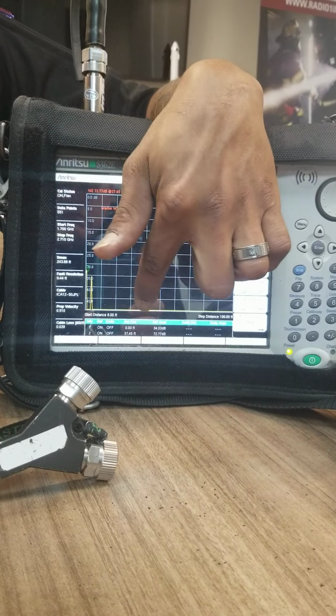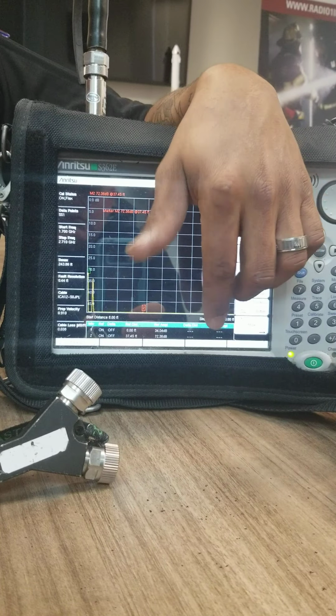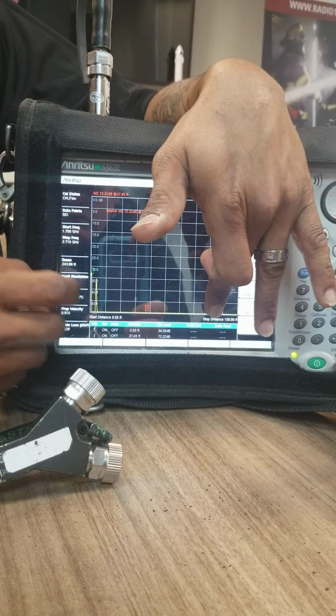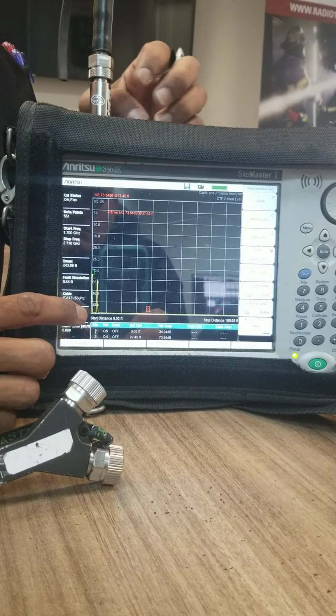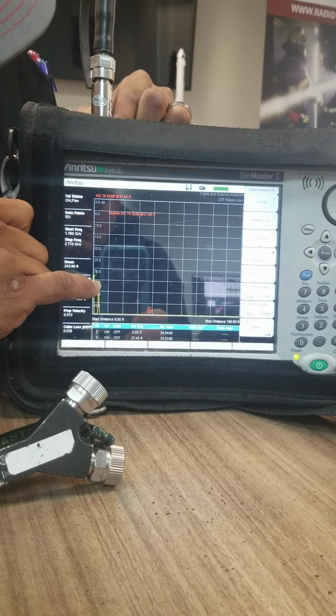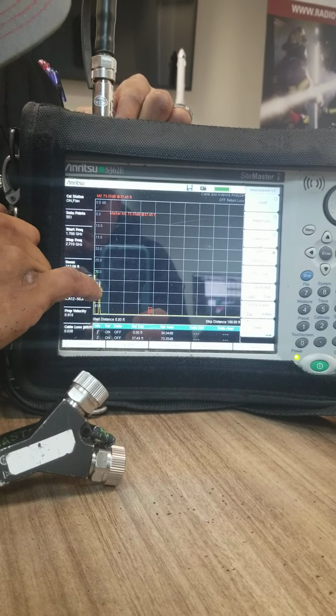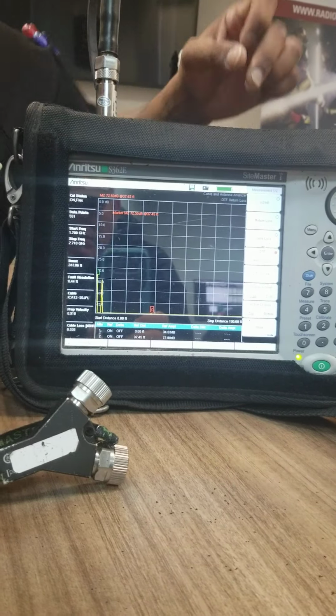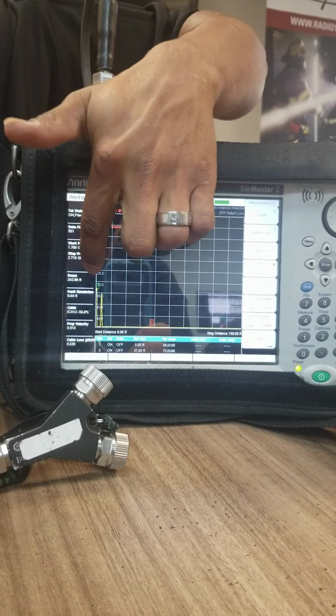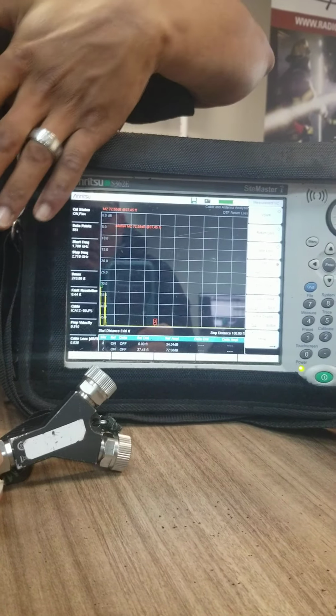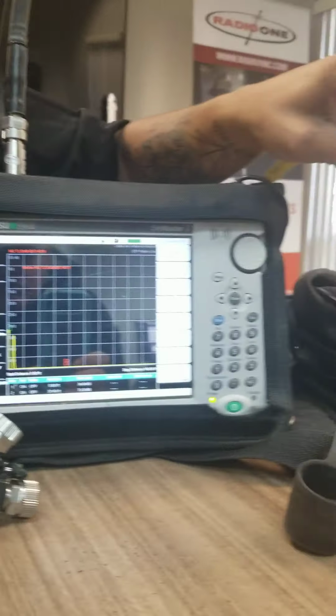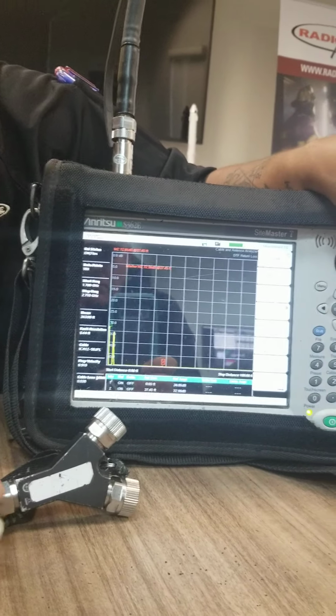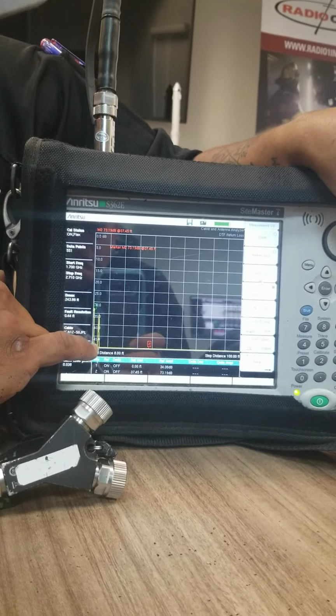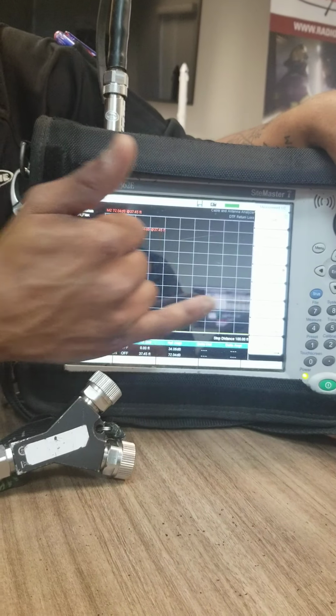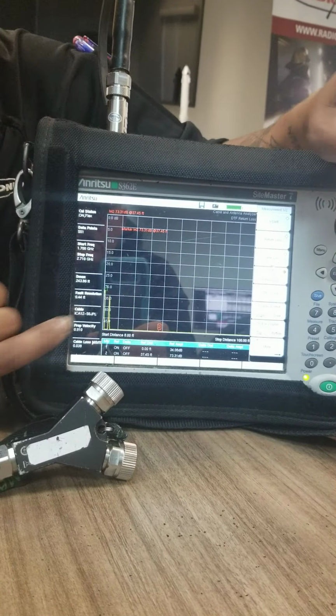You know what I'm saying? So if you see any spike between the connectors, right? When you have one spike at the connector here and one like this, you see how now it gets better. So this is one connector and this is the other one. This one right here is my low side, the one close towards me. This is your cable, it's your fake cable. Now between them, you gotta make sure it's flat. If you see any spike between those connectors, that's a kink.